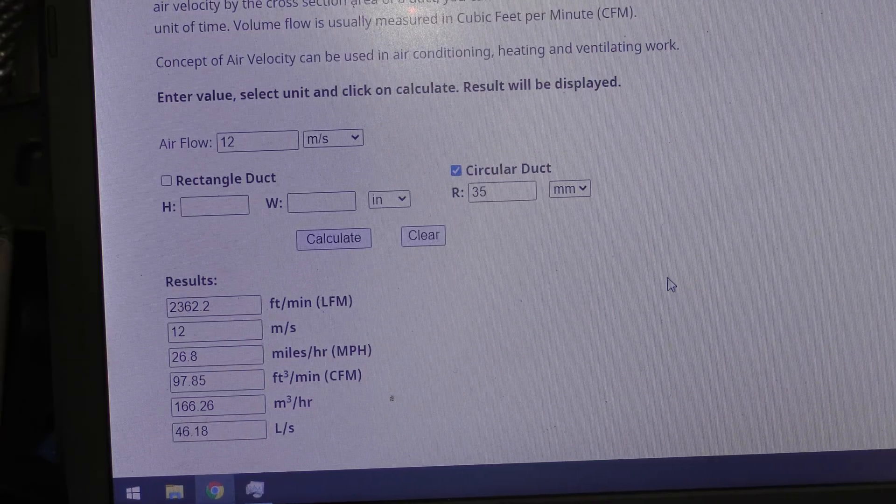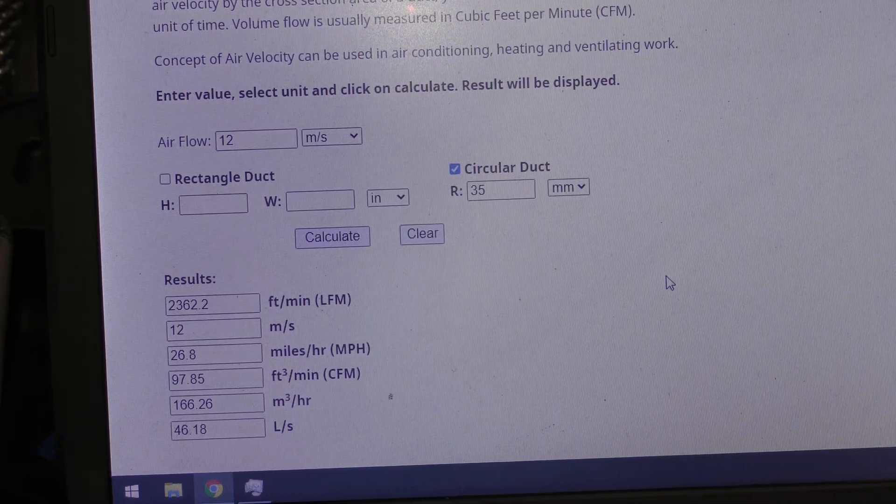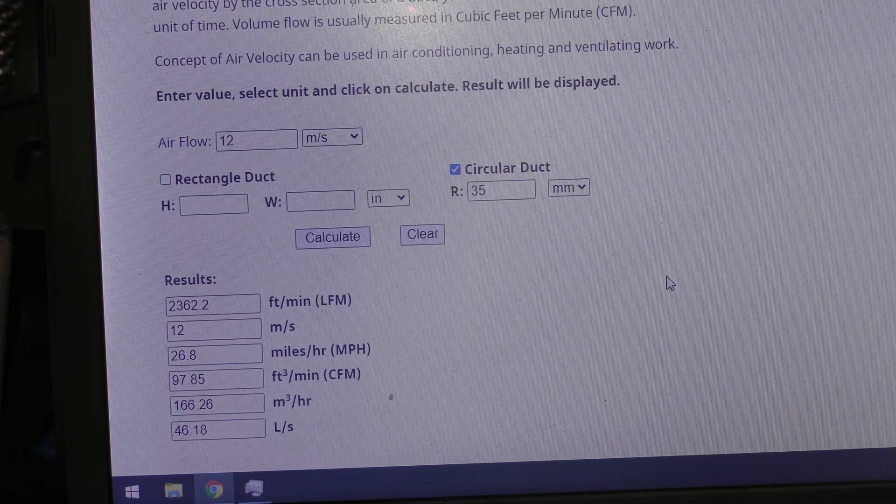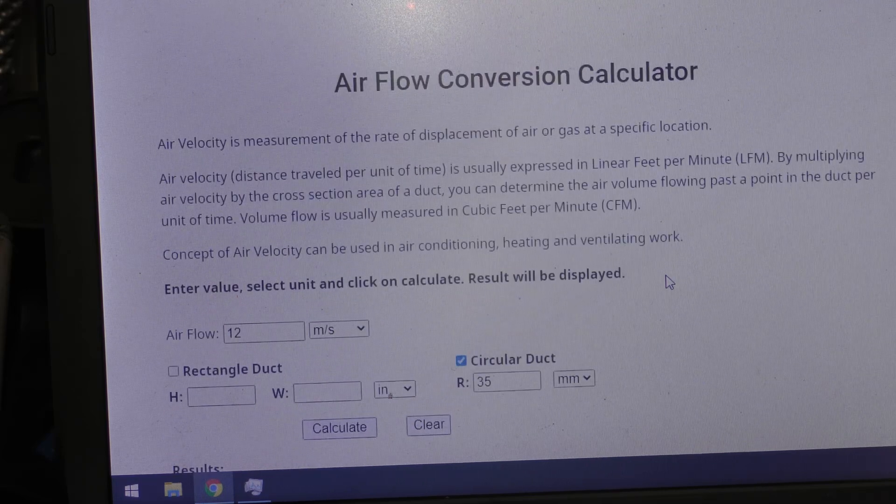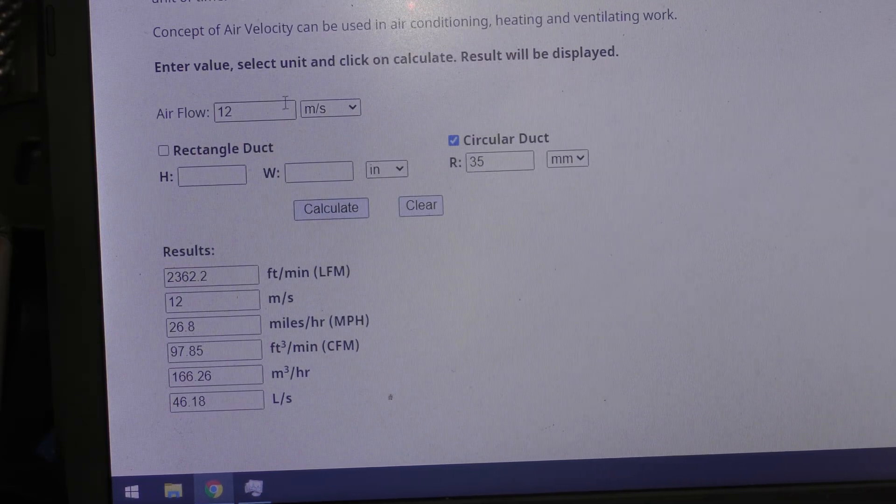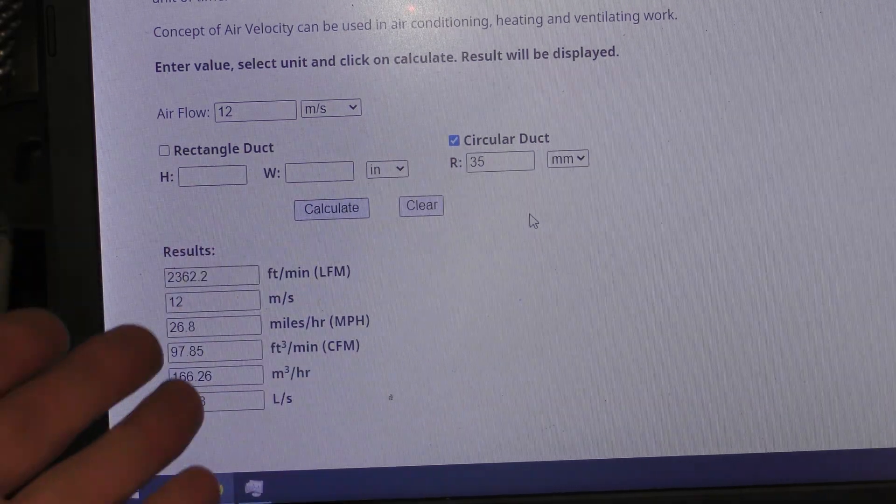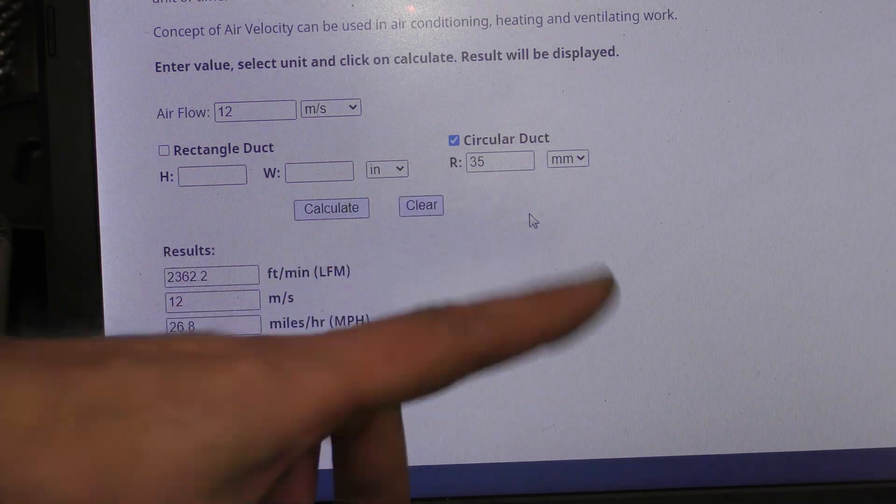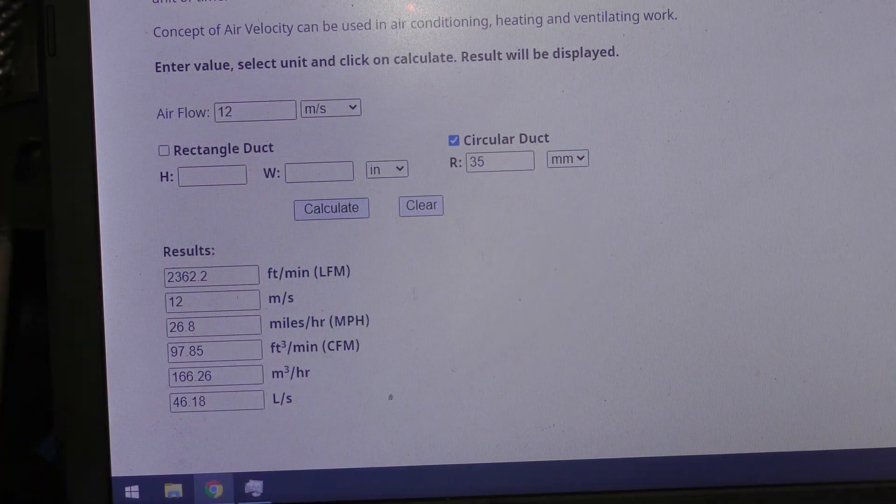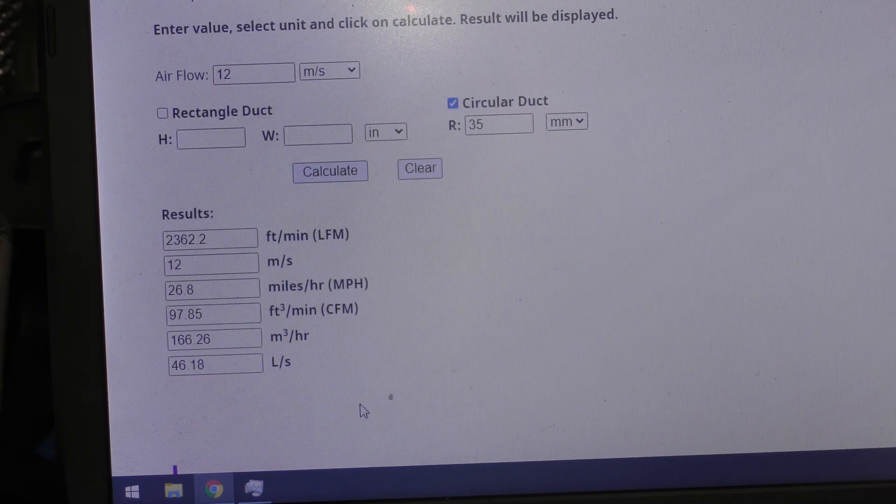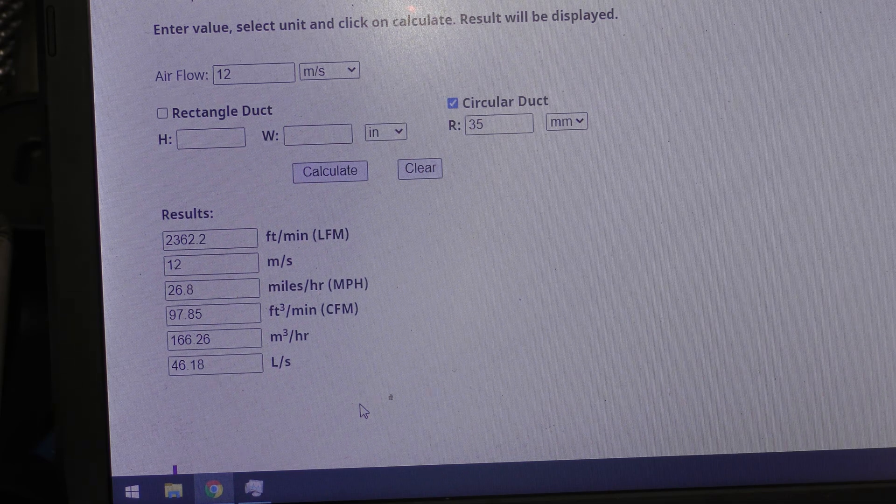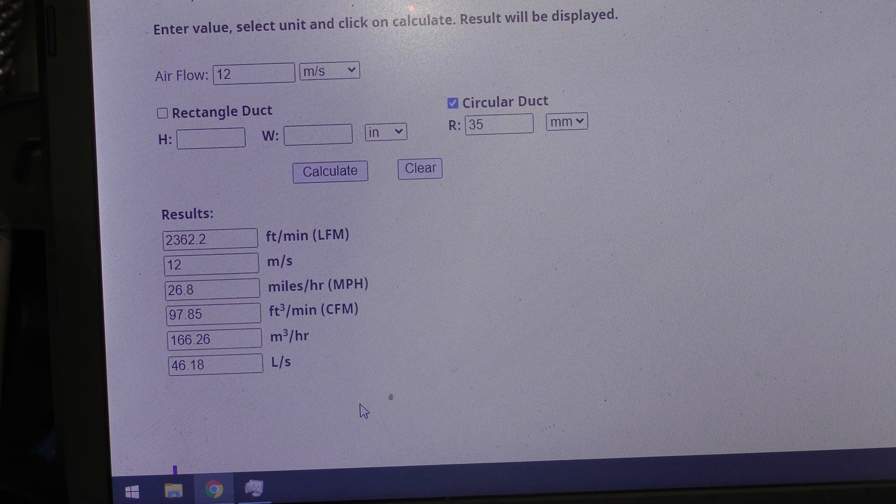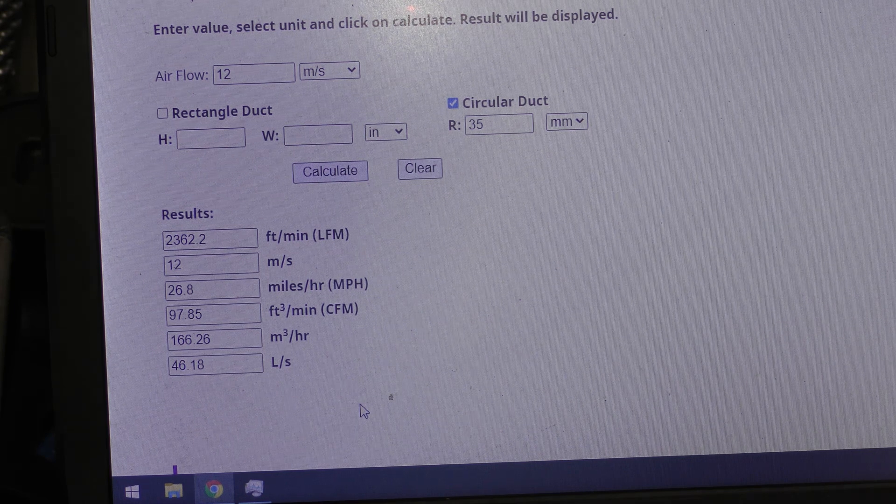So the first thing we need to work out is converting our air flow in meters per second into the weight of the air that we have moved. So there's this online calculator which you put in your air flow which ours was 12 meters per second. The size of our ducting is in radius so 35 millimeters and that gives us 166.26 meters cubed per hour of air.